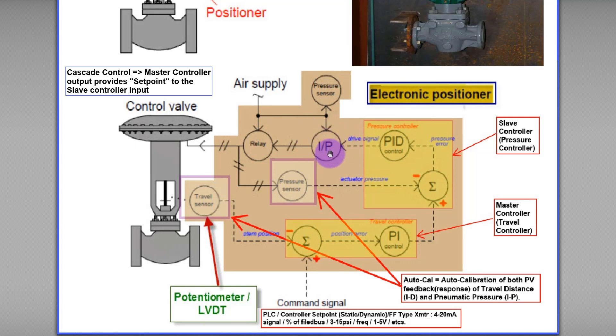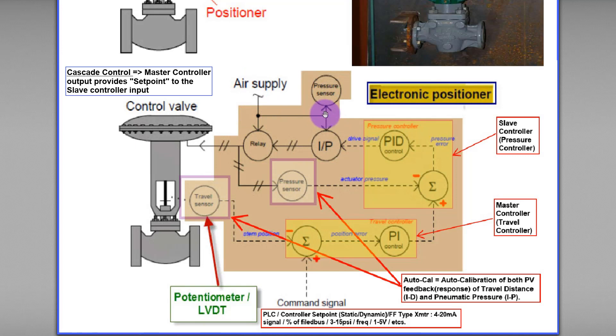The slave pressure controller produces a drive signal to the I/P transducer — sometimes called an I/P converter — which is a current-to-pneumatic pressure converter. It converts the current input to a pneumatic pressure output. Instrument air pressure is supplied to the I/P transducer, and its pneumatic output is fed to a relay, which acts as an amplifier to either increase or reduce the pneumatic air pressure.